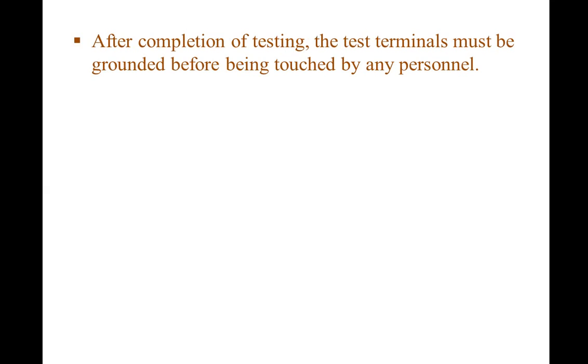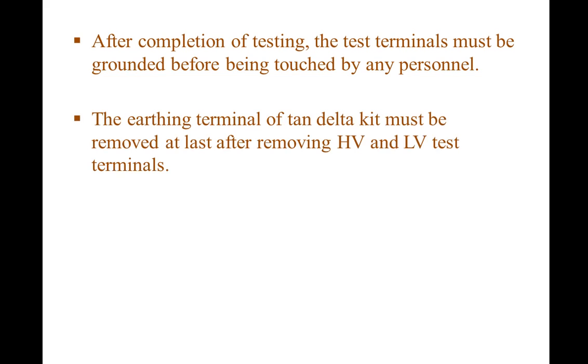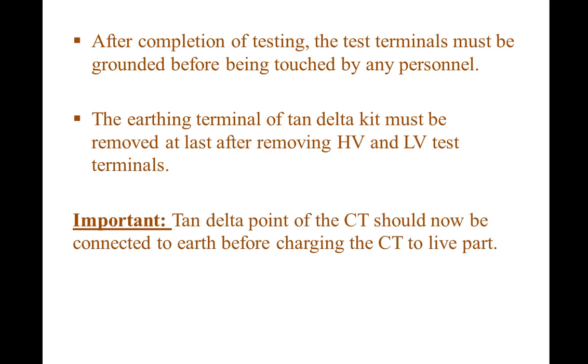After completion of testing, the test terminals must be grounded before being touched by any personnel. The earthing terminal of the tan delta kit must be removed last, after removing the HV and LV test terminals. Important point to note: the tan delta point of the CT should be connected to earth before charging the CT to a live part.